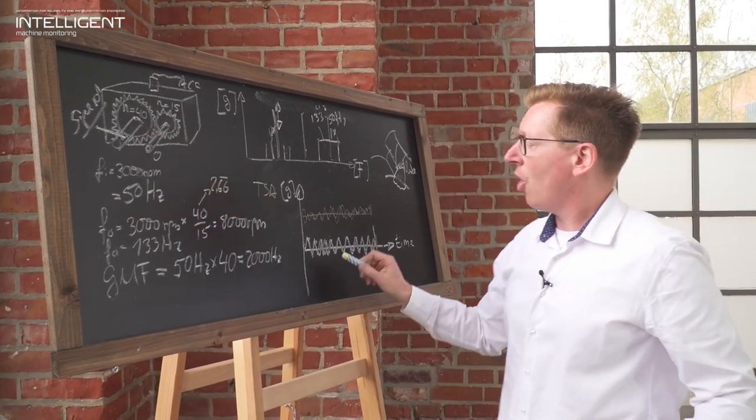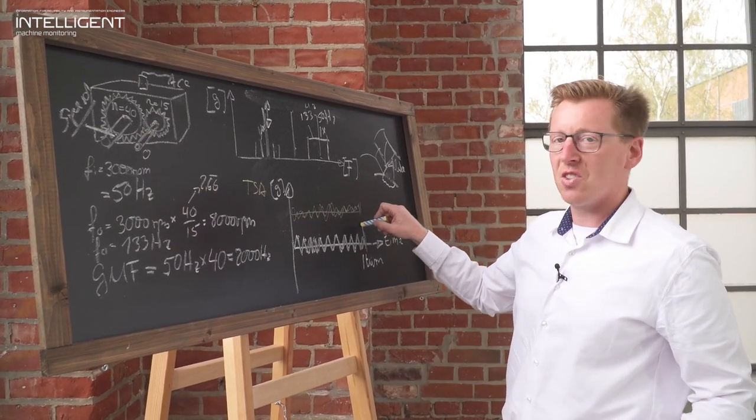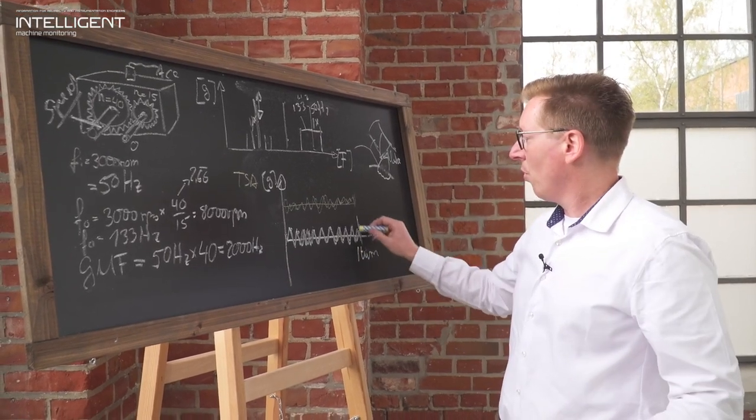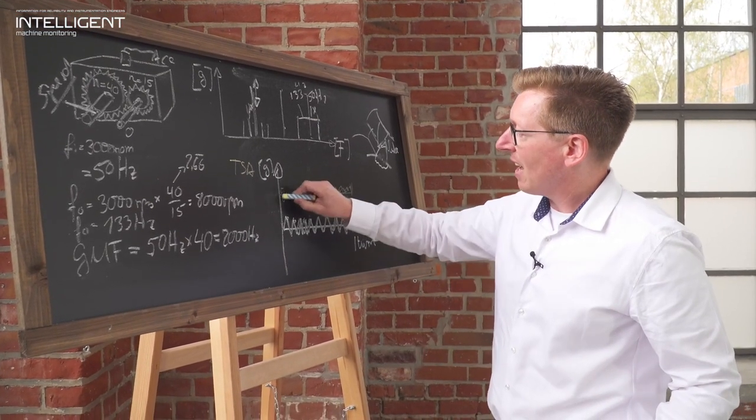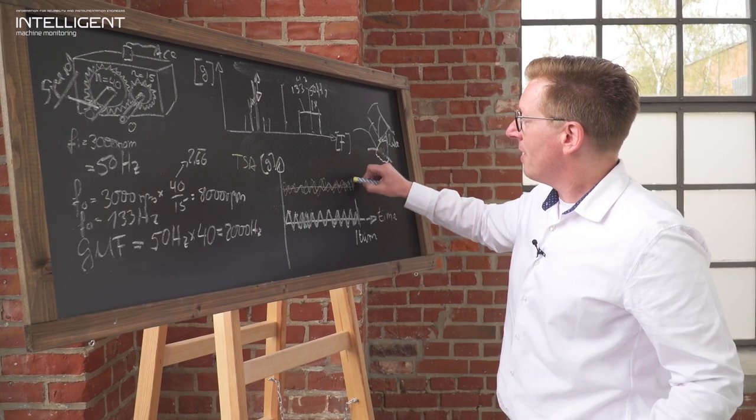The same would be applicable for a TSA. If you limit the full turn to the 15 tooth wheel, the 40 tooth wheel will not influence the TSA because it's not synchronous. It's not synchronous to the full turn data acquisition and will over time eliminate itself.